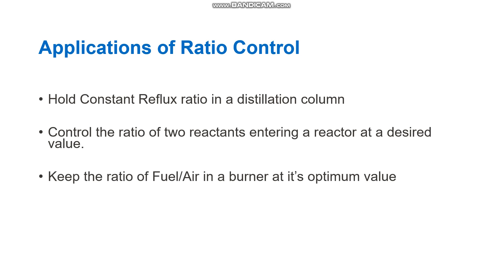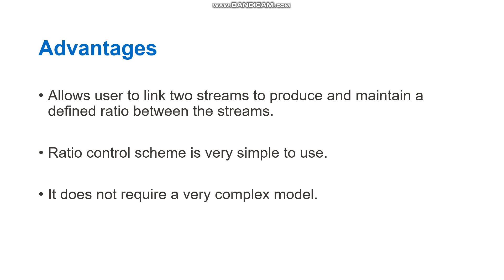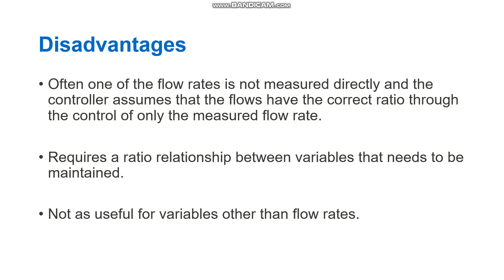The advantages of ratio control are that it allows the user to link two streams to produce and maintain a defined ratio between them. This scheme is very simple to use and does not require a very complex model. A disadvantage is that one of the flow rates may not be measured directly, and the controller assumes the flows have the correct ratio through control of only the measured flow. It also requires a ratio relationship between variables, and is not very useful for variables other than flow rates.